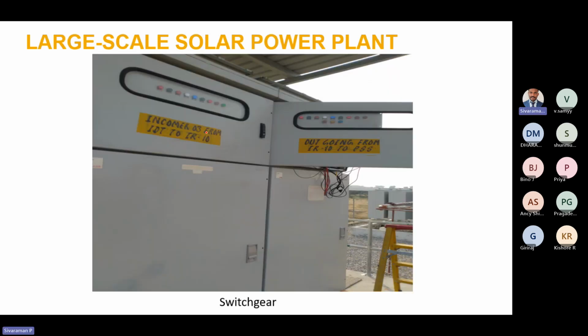Okay, and this is the switch gear, the closer view. Here you can see incomer 03 from IDT 10, IR 10. What it means is from the inverter room 10, the incoming feeder is coming like this. This is IR10, inverter room 10. From here the cable is coming here. There is a VCB in this location. Then after that there will be a bus here. This will be a bus. In this bus the outgoing feeder is here.